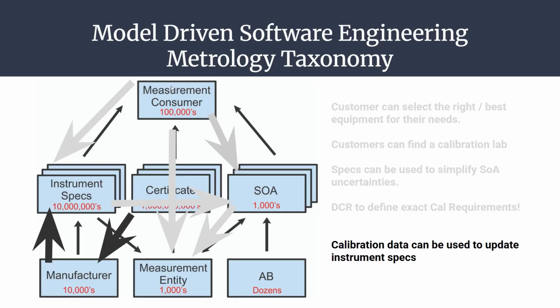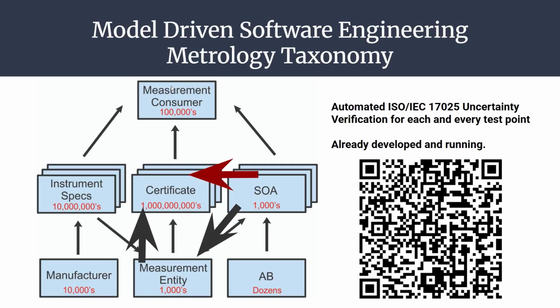So, another thing that's kind of advanced, but as we get into big data, imagine that manufacturers can use the historical calibration of the assets that are out there, and they could go back and increase their specifications or decrease their specifications, because when they did the study, when they made it, they had a wide margin because they weren't sure. But 3-5 years later, they discovered their equipment's behaving way better than they originally thought it would perform. Now they could come back in and lower their specifications or make their specifications look better with real world data to back it up. So there's a lot of things that we can do.